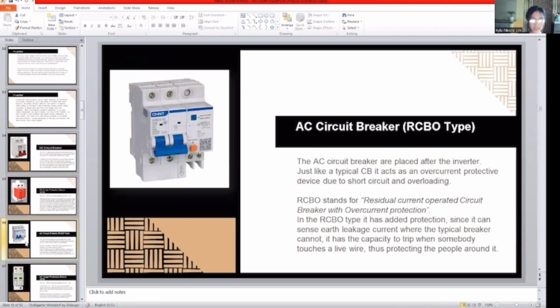arise. Next is the AC circuit breaker, or RCBO type. The AC circuit breaker is placed after the inverter. Just like a typical CB, it acts as an overcurrent protecting device due to short circuit and overloading. RCBO stands for residual current operated circuit breaker with overcurrent protection. In the RCBO type, it has added protections since it can sense earth leakage current where the typical breaker cannot. It has the capacity to trip when somebody touches a live wire, thus protecting the people around. So, ito po, AC circuit breaker siya po yung may overcurrent protection.